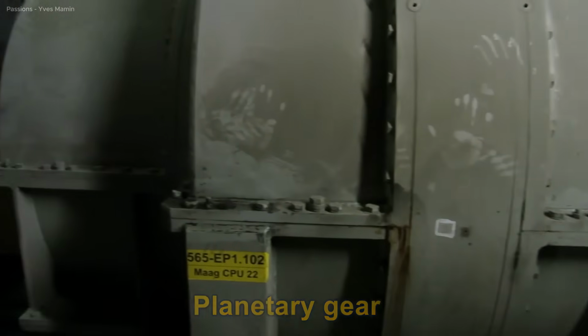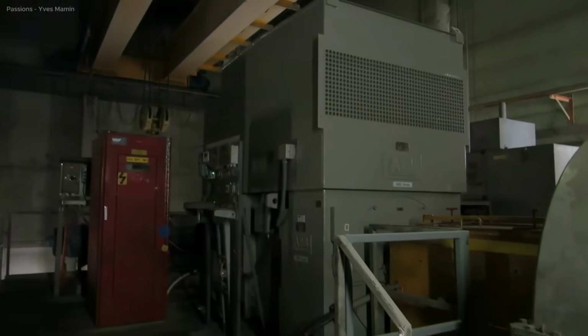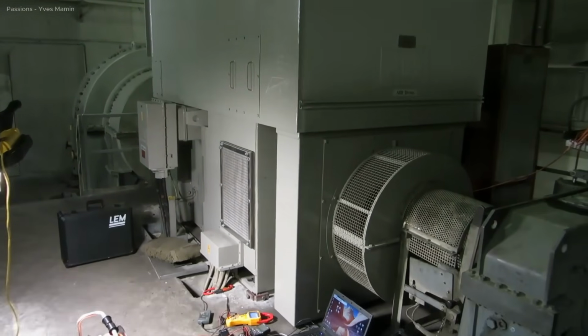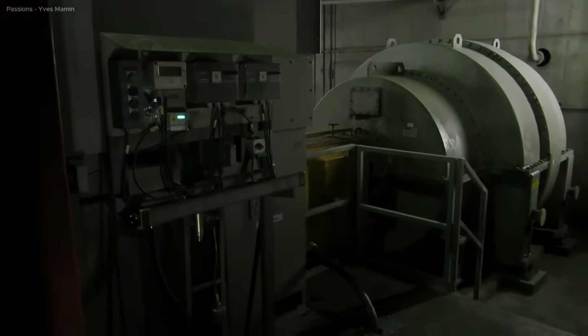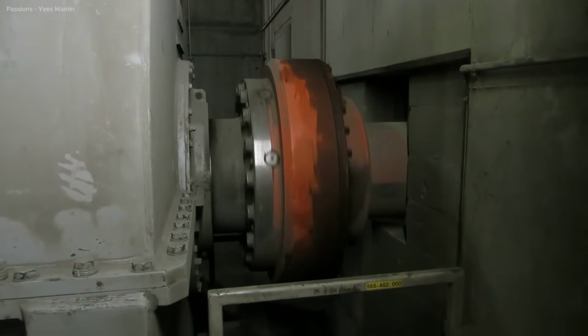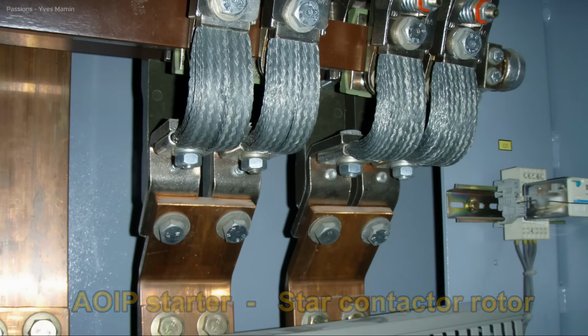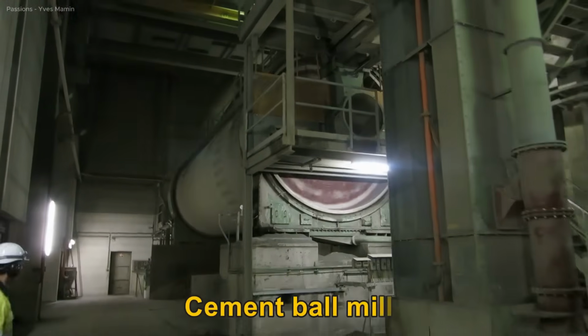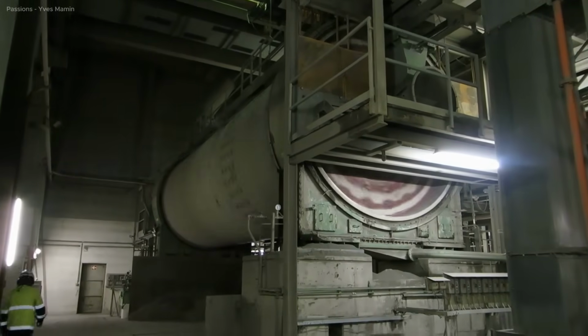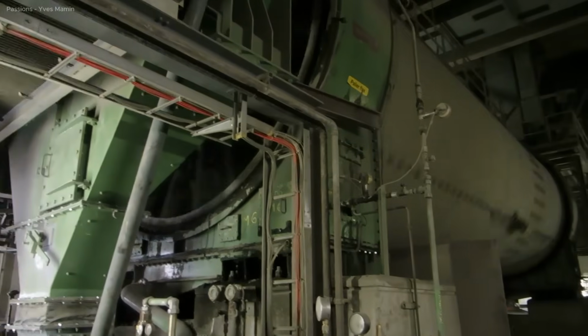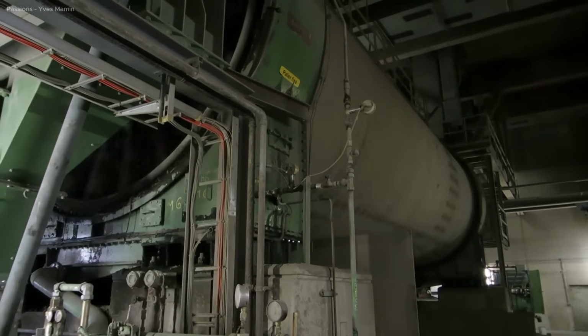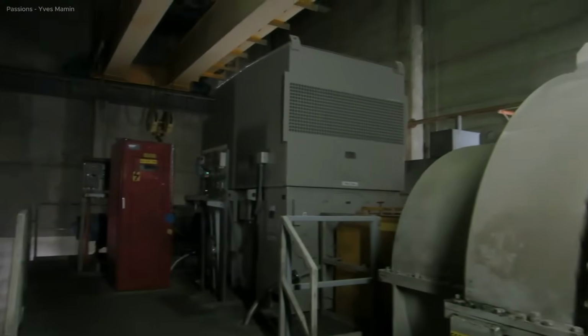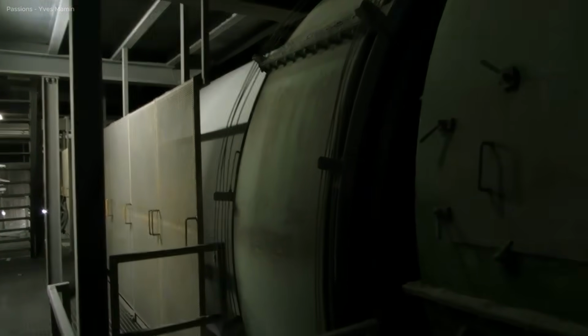The 6 kilovolts, 3-phase, 2,200 kilowatts, 1,000 revolutions per minute slip ring motor for the cement ball mill is started using an AOIP liquid resistance starter with a star contactor on the rotor circuit. At startup, resistance is inserted into the rotor to limit inrush current and provide smooth torque. As the motor accelerates, the resistance is gradually reduced in steps by the AOIP controller. Once full speed is reached, the rotor circuit is short-circuited via the star contactor. The motor then drives the cement ball mill through a planetary gearbox, ensuring stable and efficient operation.